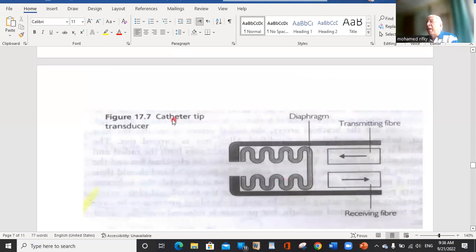This is the catheter tip transducer, with which we can measure arterial pressure inside the body, whether pulmonary artery pressure or the CVP pressure. It's made of a mirrored diaphragm, and we have an incident and reflecting light. Of course, this mirror is bent by the pressure, either becoming concave or convex, and it will affect the reflecting light. This reflection, of course, will give me a hint about the mechanical pressure changing the configuration of this diaphragm.